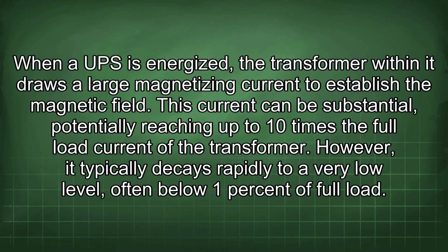When a UPS is energized, the transformer within it draws a large magnetizing current to establish the magnetic field. This current can be substantial, potentially reaching up to 10 times the full load current of the transformer. However, it typically decays rapidly to a very low level, often below 1% of full load.